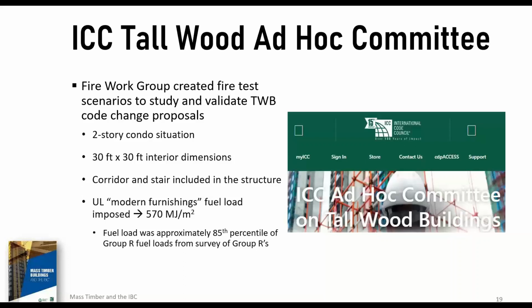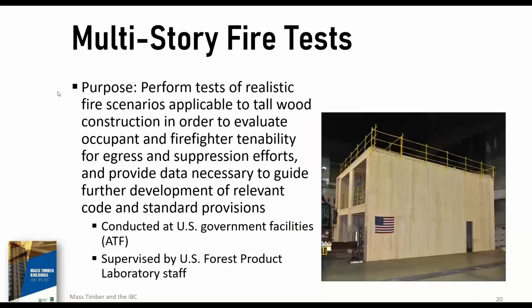So the fuel load was determined by a survey of group residential occupancies, and they determined that the fuel load was approximately in the 85th percentile of all those occupancies that were evaluated under the residential occupancy. So, a multifaceted purpose for the tests. They wanted the test to be realistic to evaluate the safety of both occupants and firefighters during egress and suppression efforts, and also to capture as much data as possible to support further development of relevant codes and standards provisions.